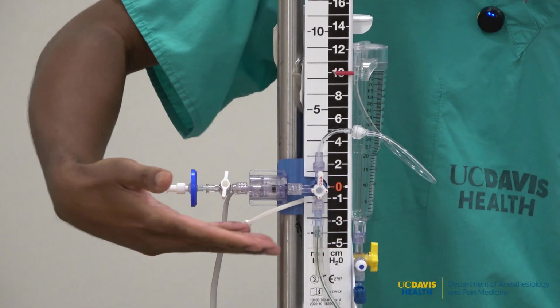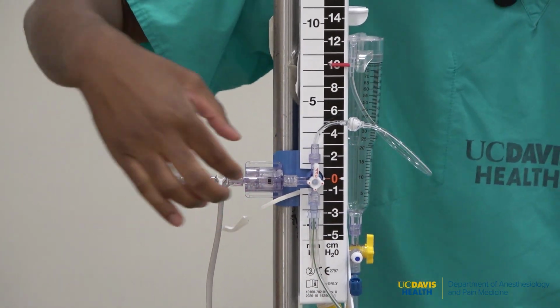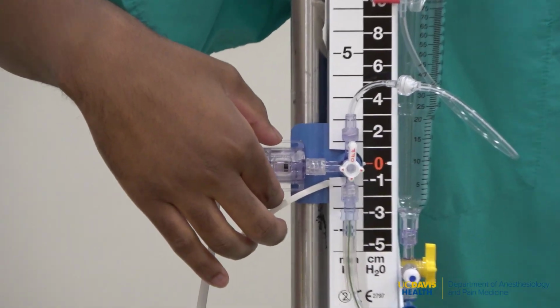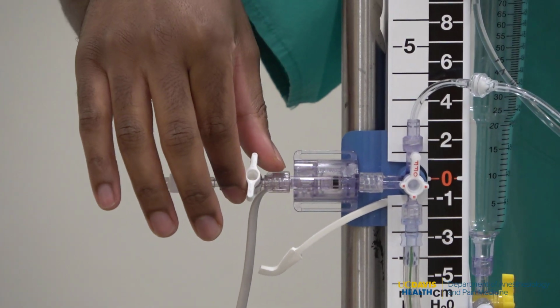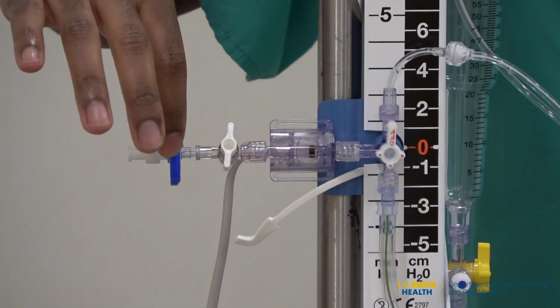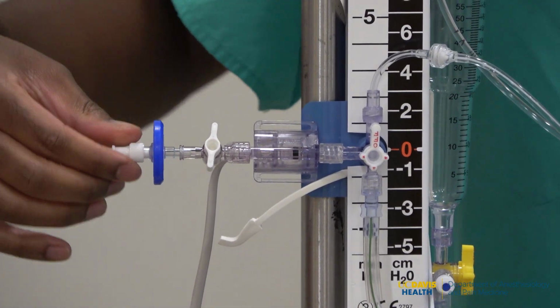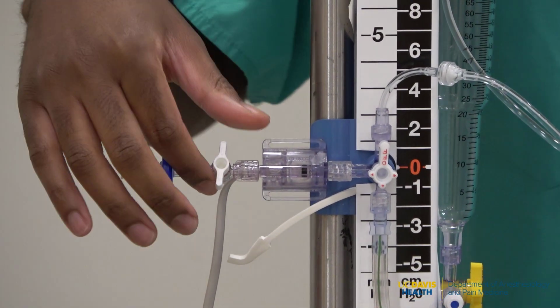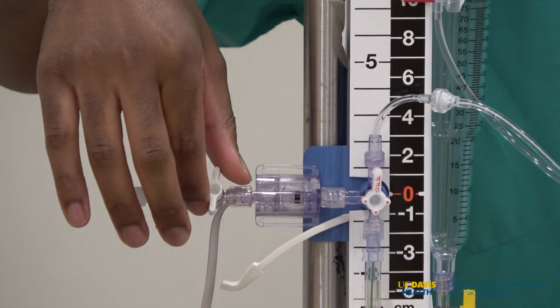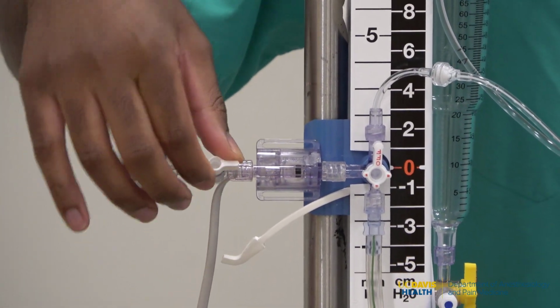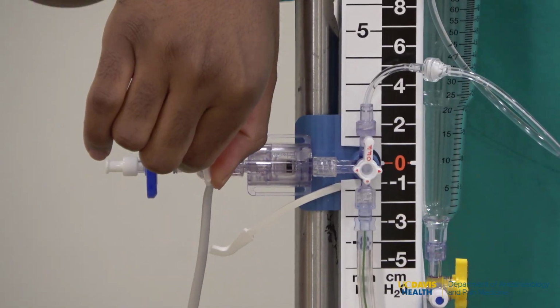This section right here is the transducer itself. This is the transducer portion. This is another stopcock, and this is a filter, and then this is a small cap. So when we want to zero the EVD, we would essentially have to have this open. Otherwise, it should be closed.